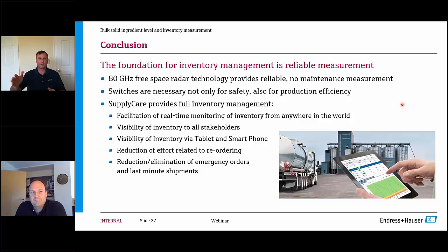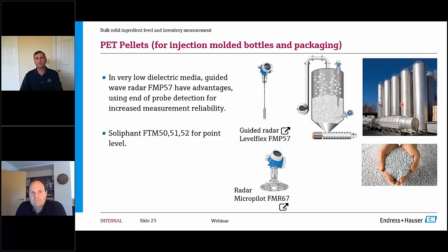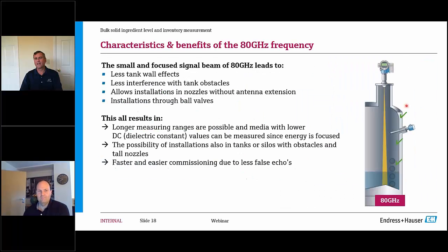I guess maybe the question is, what if I have a domed roof, and you're not able to have a flange which is level like this? I guess you could mount it like that and then aim it. But in my experience, most flanges are mounted horizontal to the liquid level. So could you use it? Yes. I struggle to see when and where that would be necessary.